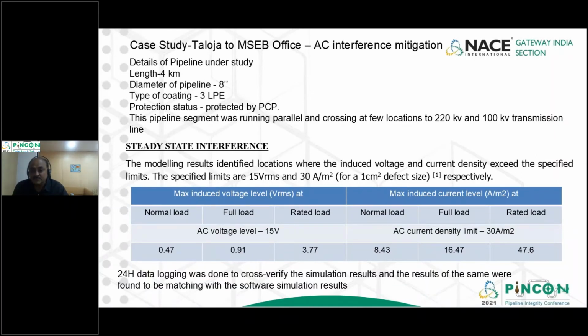15 volts and 30 amps per meter square. So for the normal load, full load, rated load, if I look at the maximum induced voltage levels, the AC voltage limit is 15 volts, and the current density as per the standard is 30 amps per meter square. What we were getting here at normal full load and rated load was around 3.7 volts, so voltage was not a big issue. For the induced current at normal full load and rated load we were getting 47.6, at a particular location. So 24-hour data logging was done to cross verify the simulation result, and the results were found to be matching with the software simulation results.